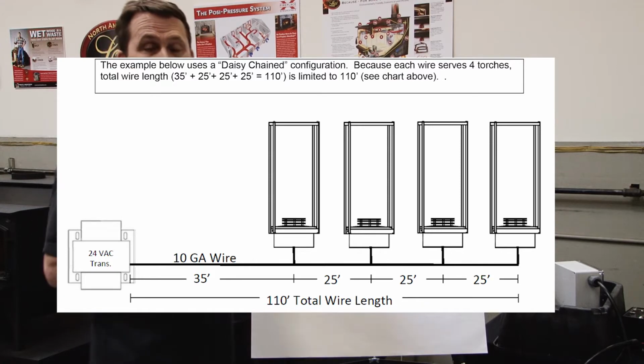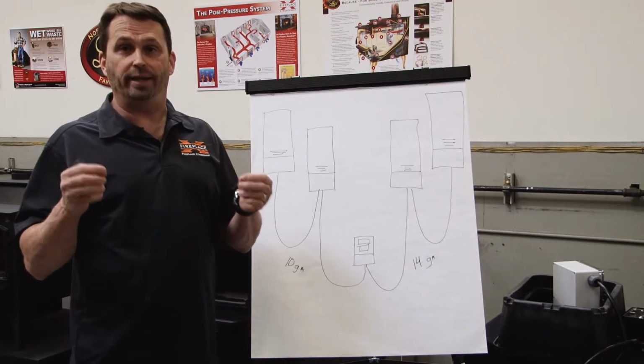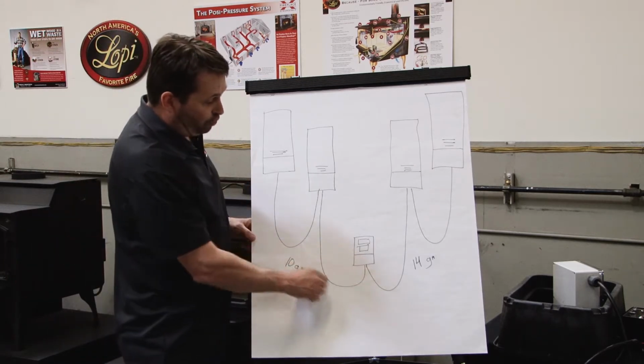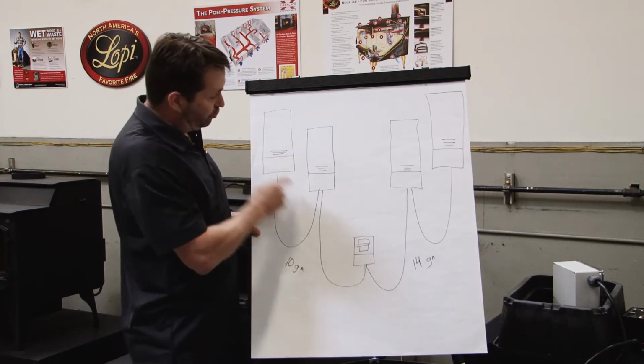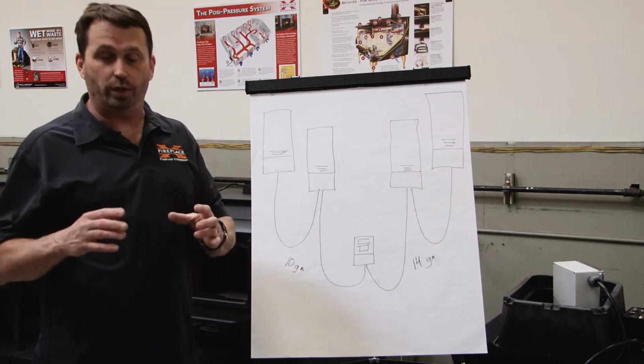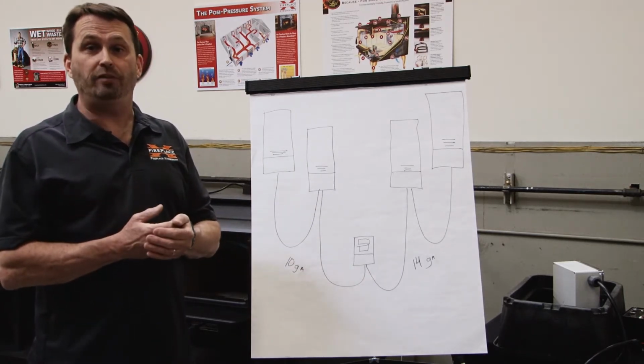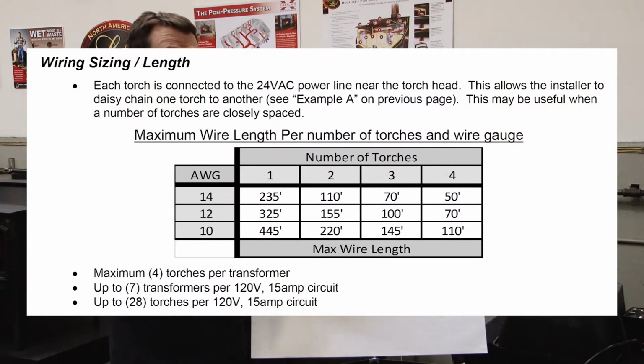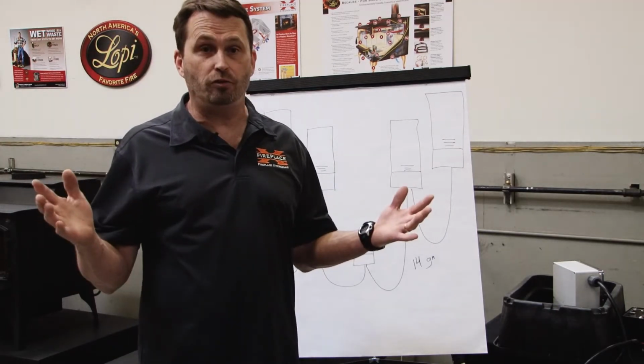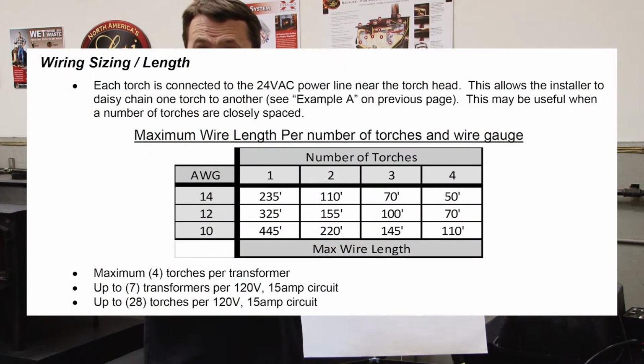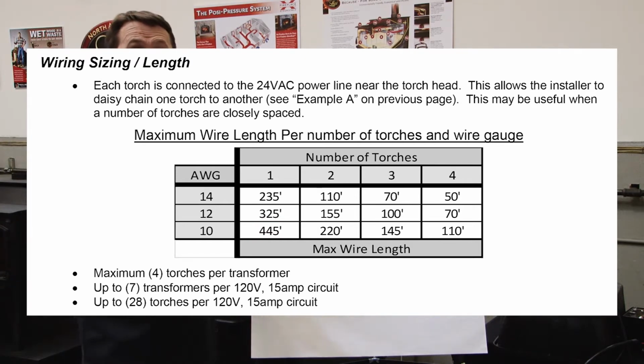So when you're daisy chaining the appliance, the total wire run distance you have in your electrical chart accounts for the total amount of wire you have between the transformer and the end torch. So if you take a second to look at the wire chart guide for a piece of 10 gauge wire, if you have 2 torches on it, your maximum run length for that wire will be 220 feet. So the total length on a 10 gauge wire can be 220 feet of wire for 2 torches. If you have extremely long runs, a single torch on 10 gauge wire, you can run up to 445 feet. And the wiring chart applies to just the length of the wire per run from the transformer.